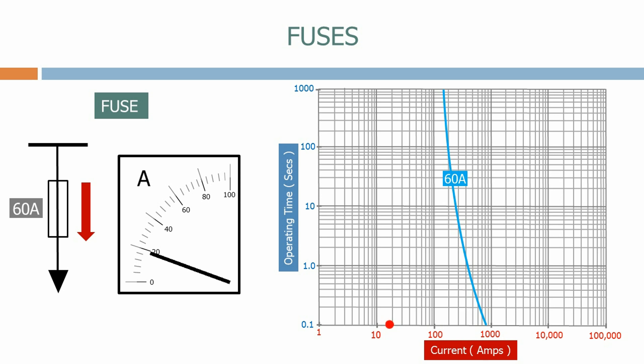During normal operation, the value of the current on the feeder will continuously vary as the load varies. During the normal operating range, the fuse will pass the current through it and not react. Therefore, this part of the fuse characteristic is called the no trip zone.